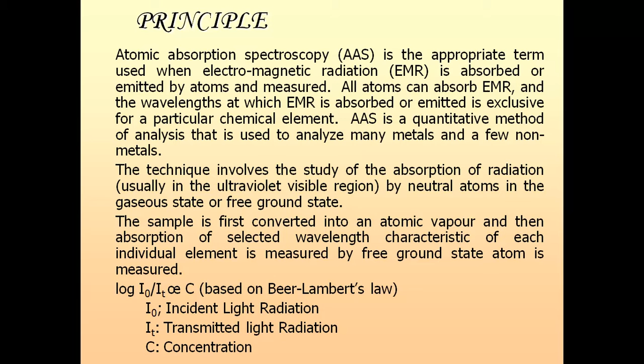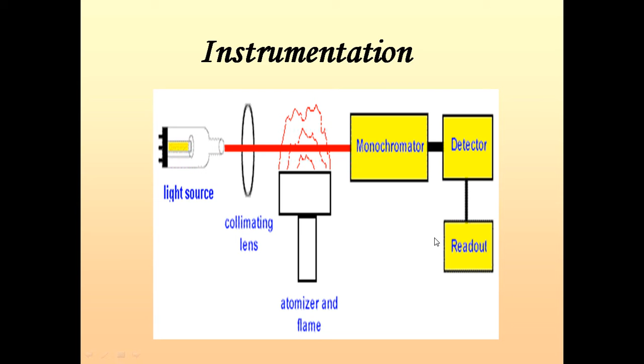This is the formula based on the Beer-Lambert law: incident light radiation, transmitted light radiation, and concentration. Instrumentation: this is the basic layout. This is the light source. It's basically a hollow cathode lamp, and this yellow part is the coating of the particular metal, and this is the anode, and this releases the radiation, and these are lenses in between. Then the samples are present in the atomization flame. This is the flame which excites the atoms from the ground state to the excited state. This is a monochromator and detector, and the readout.